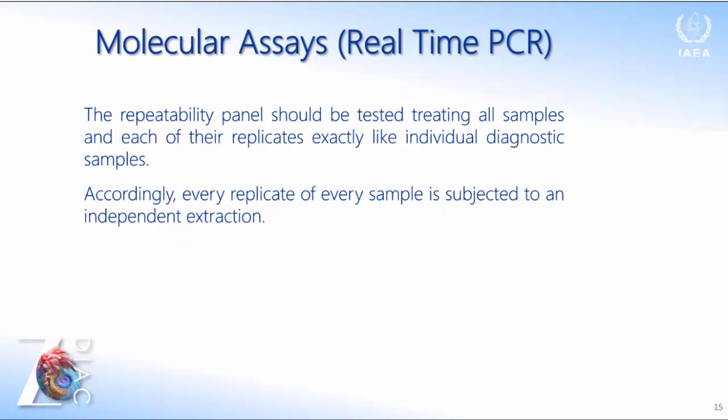The repeatability panel should be tested treating all samples and each of their replicates exactly like individual diagnostic samples. So accordingly, every replicate of every sample is subjected to an independent extraction.